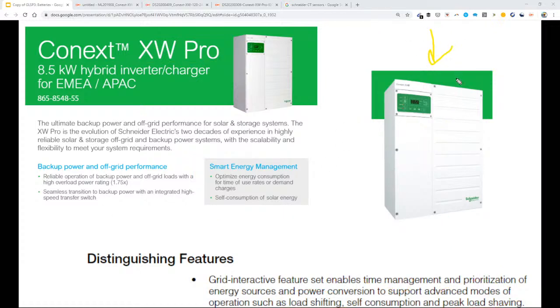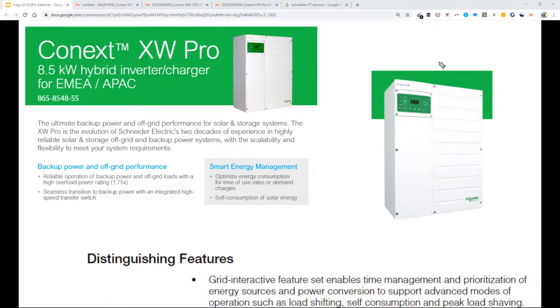All the features we've talked about so far are listed as things a battery inverter delivers, but this Schneider inverter only delivers those features on the critical load panel side it's tied into, not on the grid-connected side. So if you just want a battery inverter plugged into the grid with all these intelligent energy management features plus backup power, not all name brand battery inverters can do that. A lot of them were designed for the off-grid market where you don't need those features.